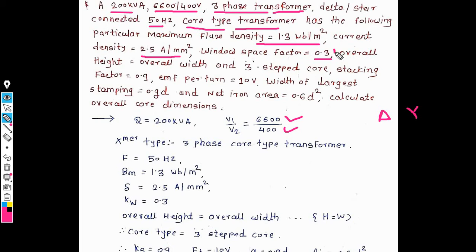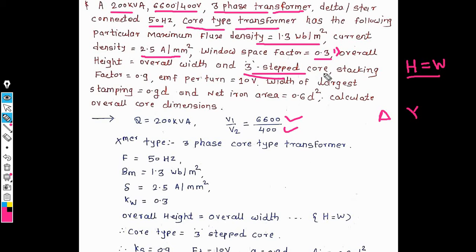The first condition is that the overall height is equal to the overall width — that is, H equals W. This is a three-phase core-type transformer in which a three-step core is used. The stacking factor is 0.9 and the EMF per turn is 10 volts.